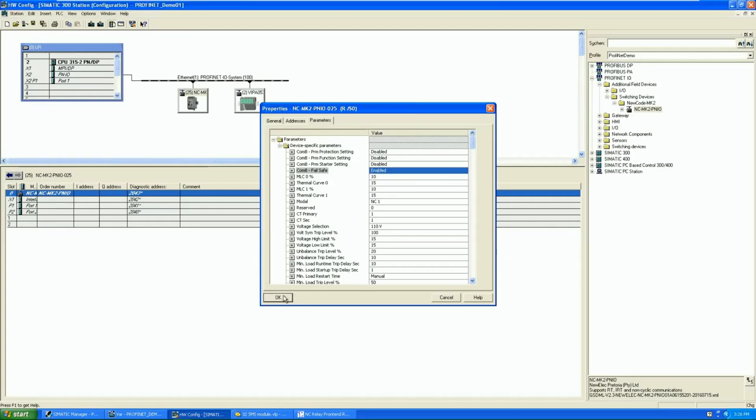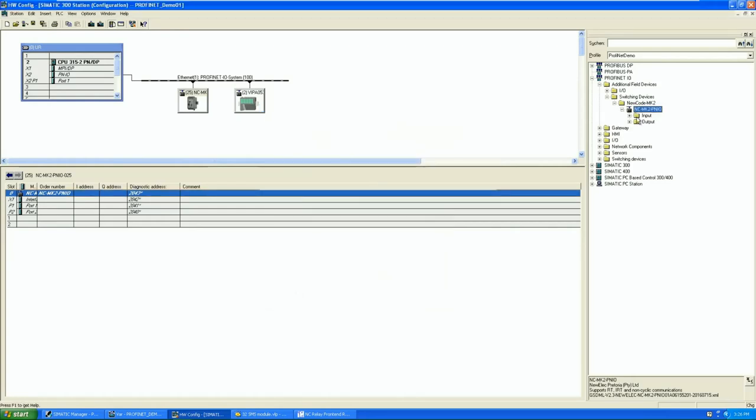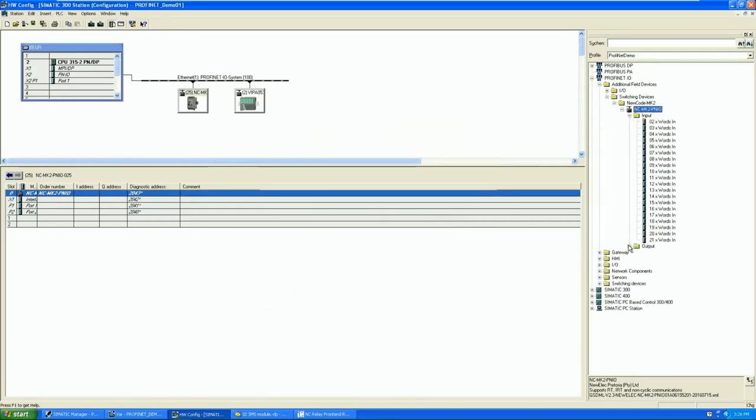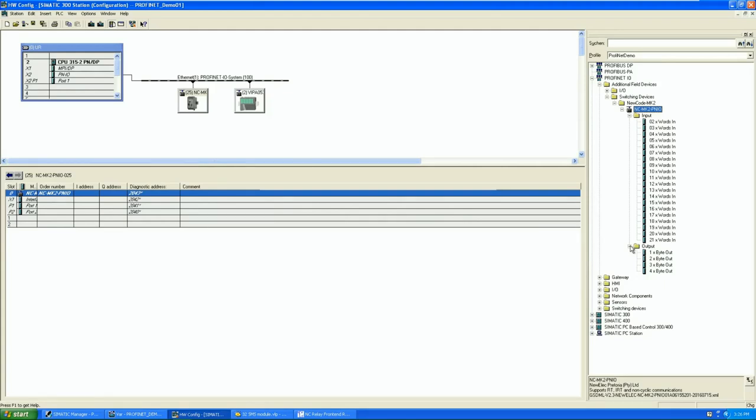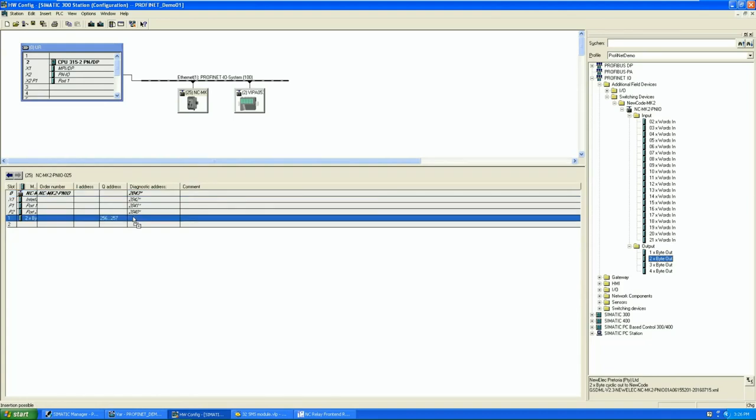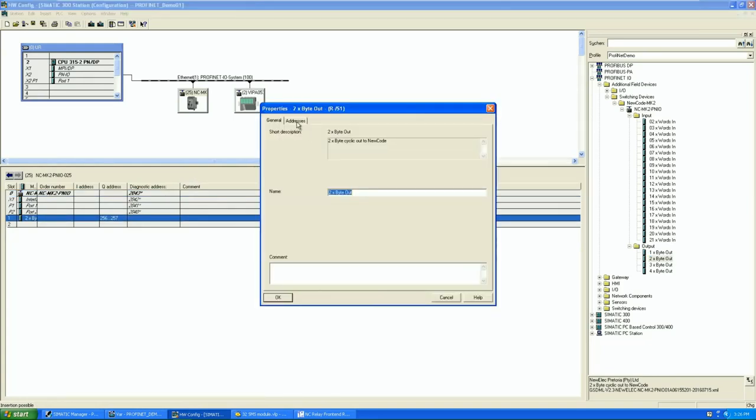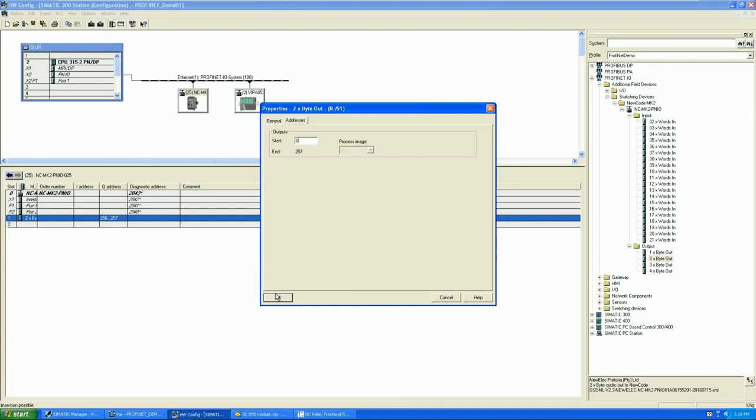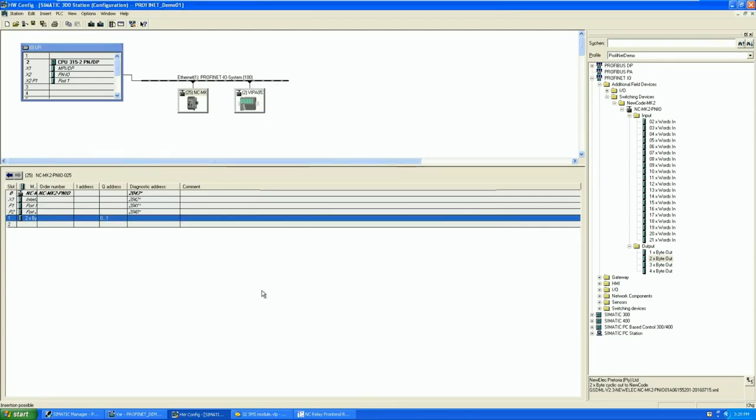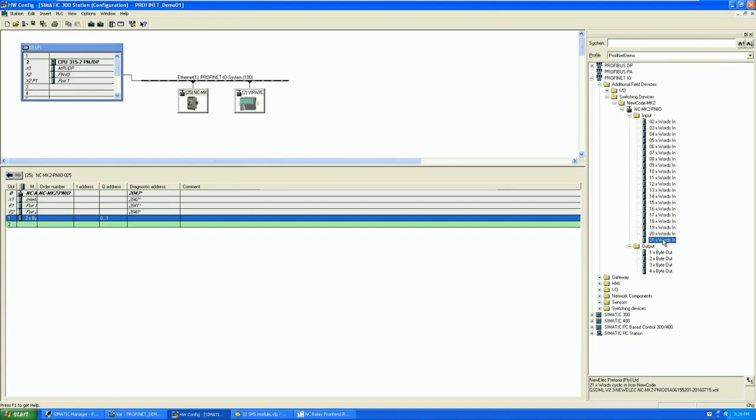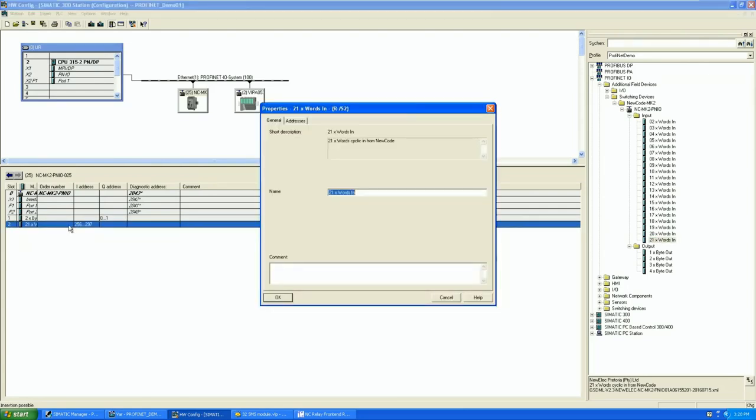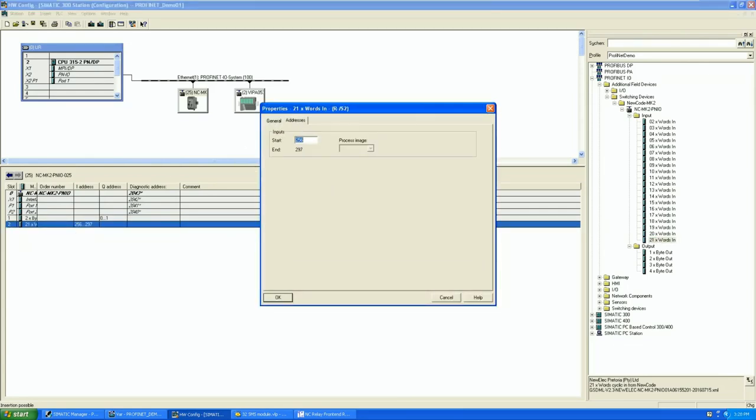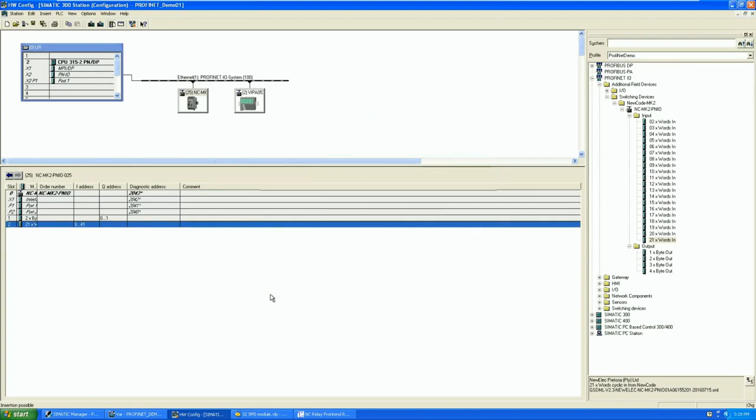After the parameters has been correctly configured, it's time to add some cyclic data. Underneath the GSD file, you will find the input words and the output bytes. Cyclic bytes from the PLC to the NewCode relay must be inserted into slot 1. The cyclic bytes from the PLC can be from 1 byte to 4 bytes. Currently in this example, I'm only going to be using 2 bytes and we're going to put them onto address 0. Cyclic words from the NewCode relay to the PLC must then be inserted into slot 2. The cyclic words can range from 2 words to 21 words. Word 1 will always be the heartbeat indication from the NewCode relay. The remaining words will be represented as structured in the NewCode relay configuration. For this example, I'm going to be using 21 words placed onto address 0. After the NewCode PROFINET module has been configured, we can save and compile and download the hardware configuration to the PLC.